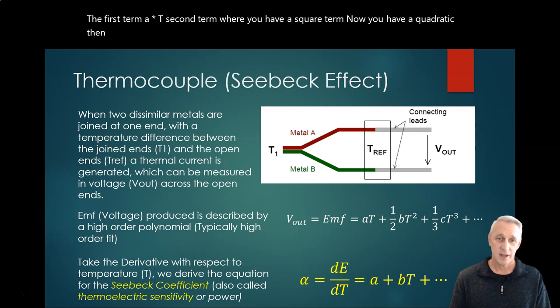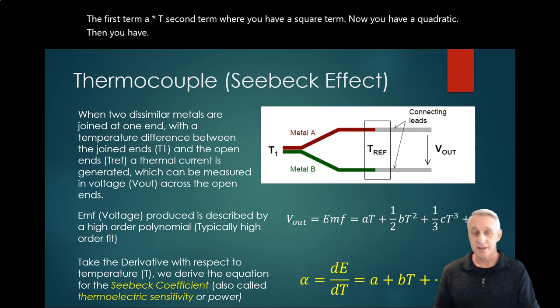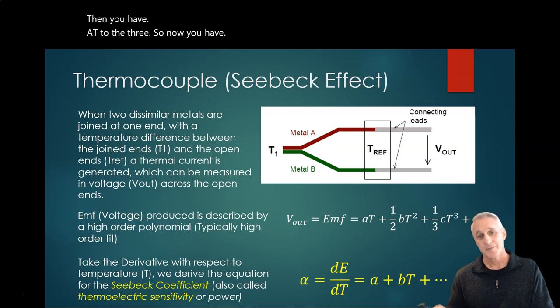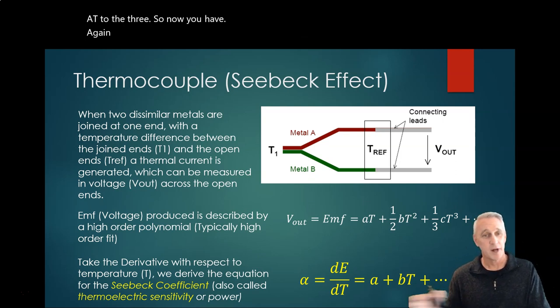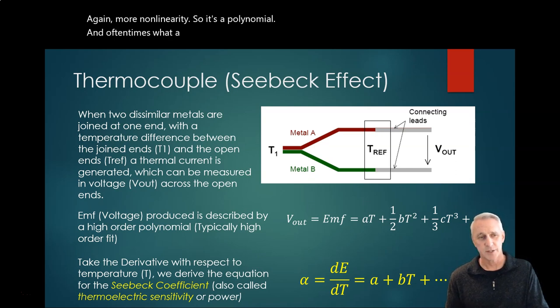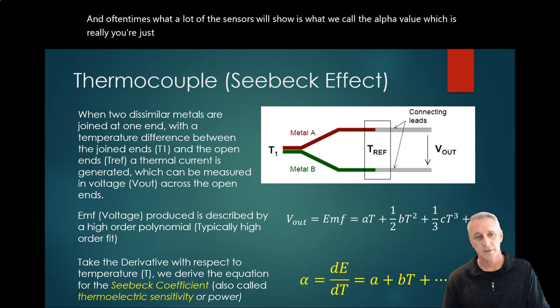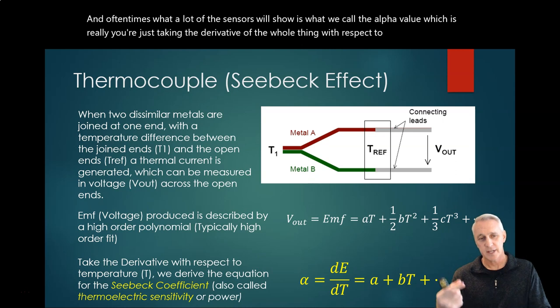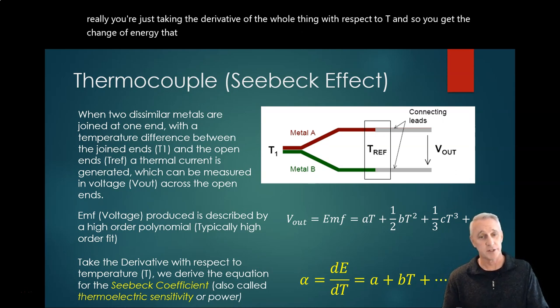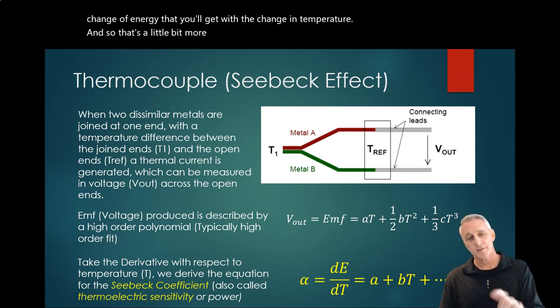Then you have T to the three, so now you have more nonlinearity - it's a polynomial. Oftentimes what a lot of sensors will show is what we call the alpha value, which is really just taking the derivative of the whole thing with respect to T. So you get the change of energy that you'll get with the change in temperature.